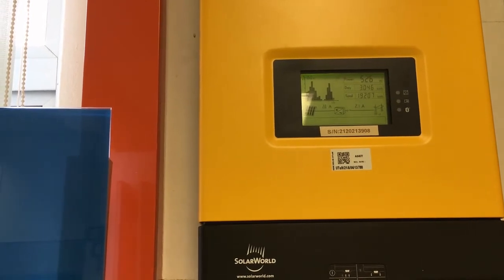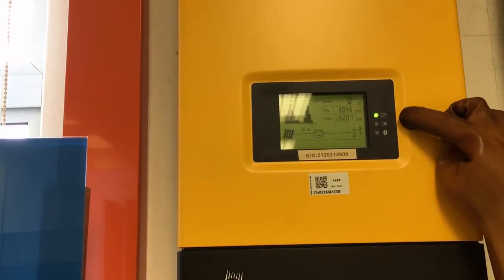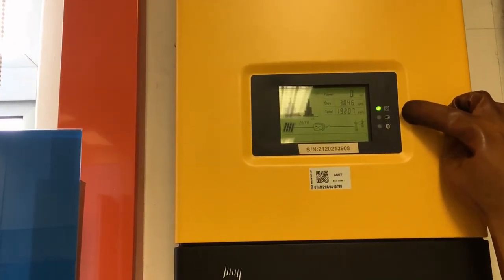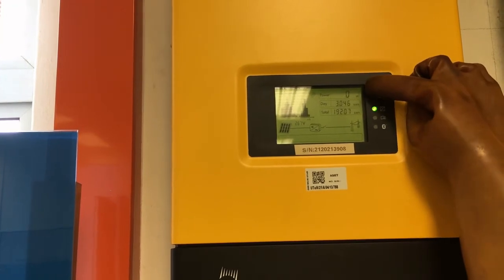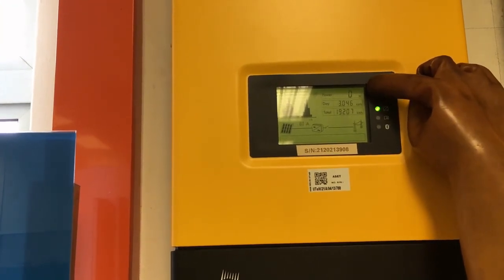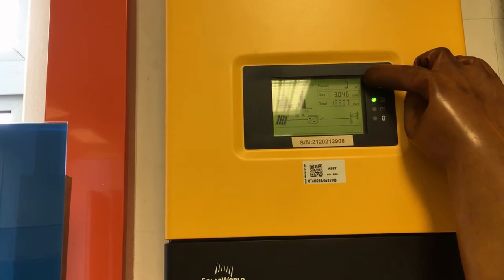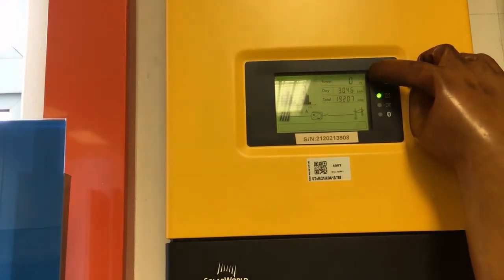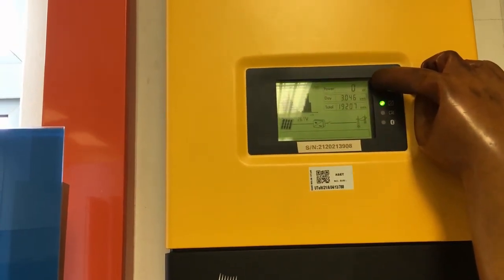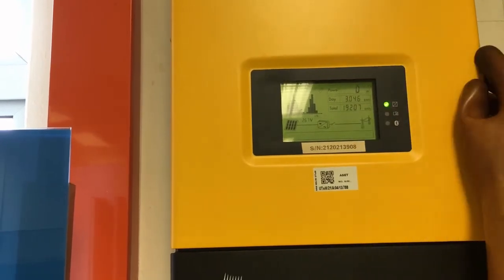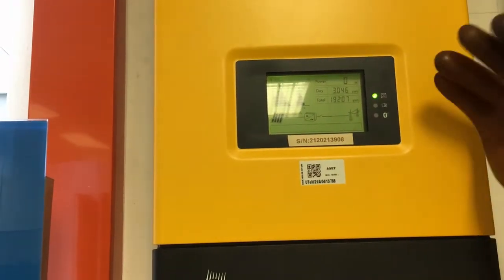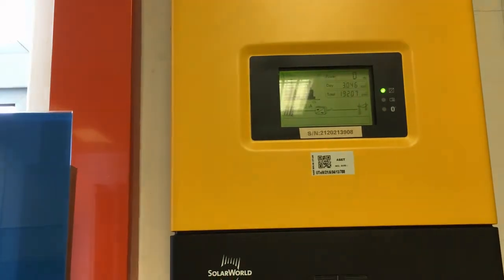Okay, I am now simulating a loss of supply from the grid. So you see that instantaneously, once I turn off the AC MCB, the light starts to blink and the power drops to 0. Right? This means now that the inverter no longer supplies power to the grid. But there is still power at the DC side.